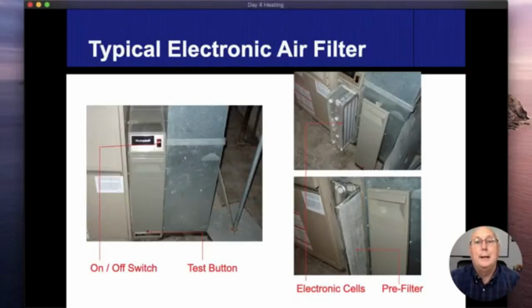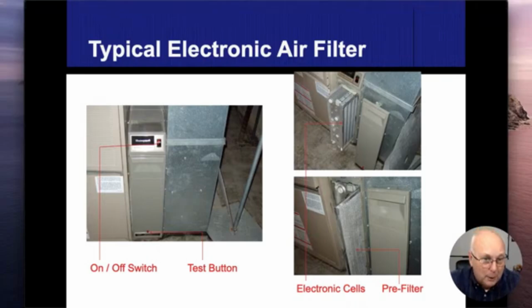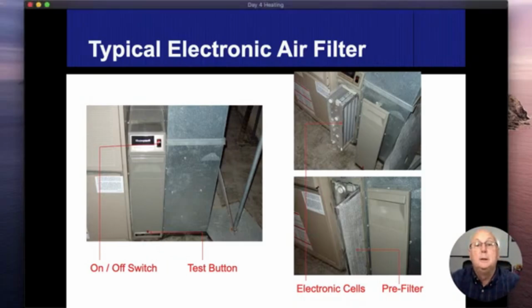So, electronic air filters, they also have certain directions. There's supposed to be pre-filters and post-filters. Those can come out and either be hosed off or put in dishwashers. I heard people get good luck with that. The other ones, it's nothing but a big bug zapper, as the dust comes in there. There is a test button typically on the bottom of these things, so that when it does run, we could press it. And if it starts clicking, then we're good. All right.